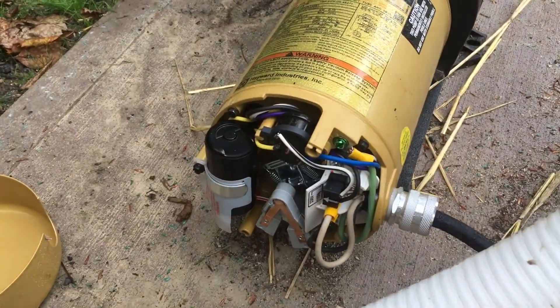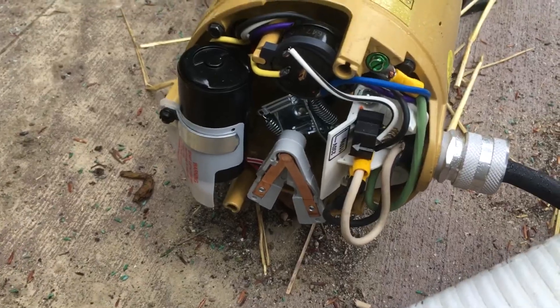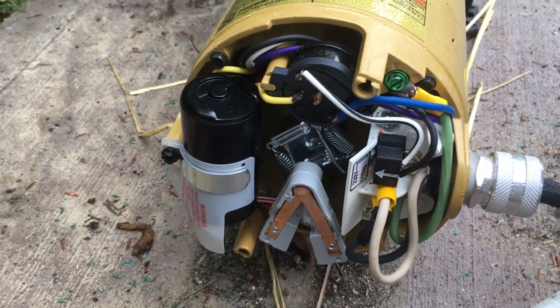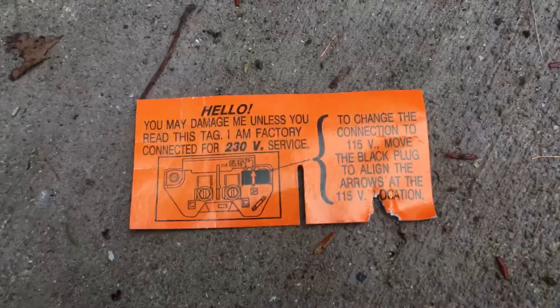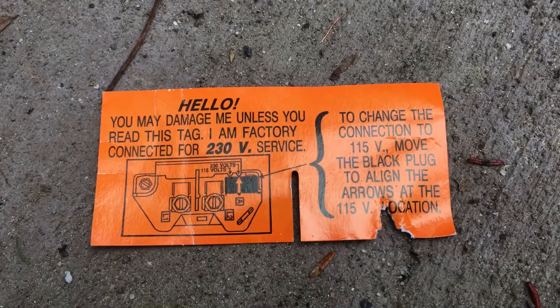This is a Hayward super pump, one horsepower. I'm trying to hook it up for 115 volts because that's what I supplied.